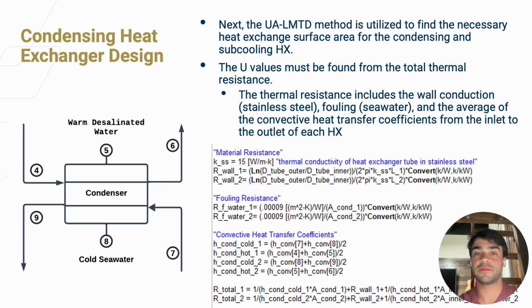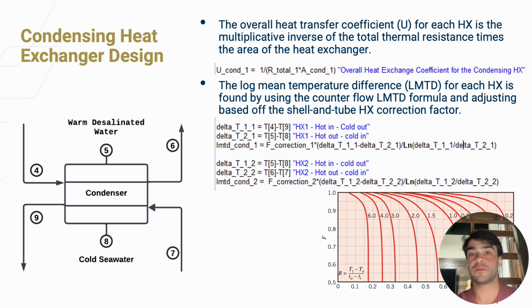We next utilize the UA-LMTD method to find the necessary heat exchange surface area. To do this, we must find the U values from the total thermal resistance, which includes the conduction across the tube wall, the fouling from the seawater, and the convective heat transfer from the fluids on the inside and outside of the tubes and shell. Once the overall heat transfer coefficient U is found for each heat exchanger, we can use the LMTD method.